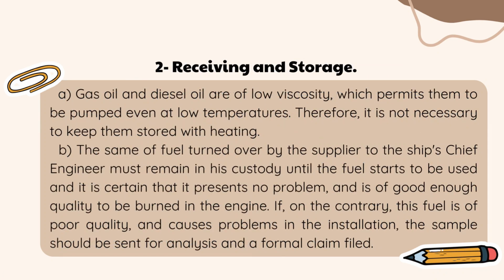2. Receiving and storage. A. Gas oil and diesel oil are of low viscosity, which permits them to be pumped even at low temperatures. Therefore, it is not necessary to keep them stored with heating. B. The sample of fuel turned over by the supplier to the ship's chief engineer must remain in his custody until the fuel starts to be used and it is certain that it presents no problem, and is of good enough quality to be burned in the engine. If, on the contrary, this fuel is of poor quality, and causes problems in the installation, the sample should be sent for analysis and a formal claim filed.